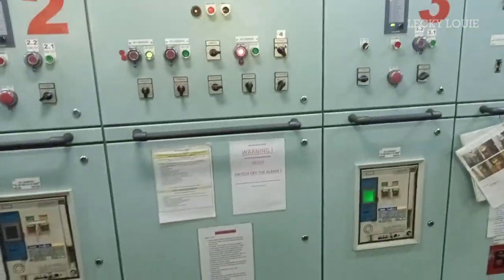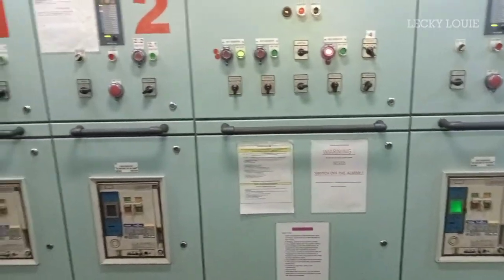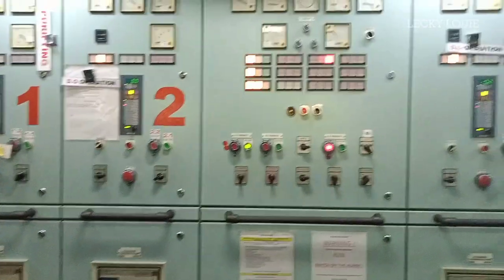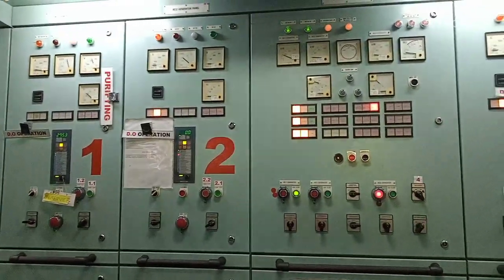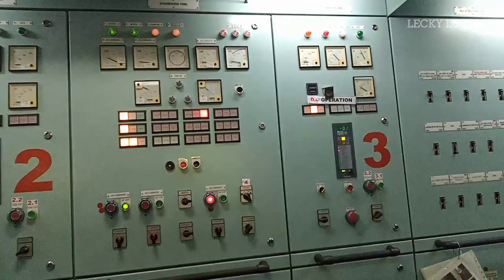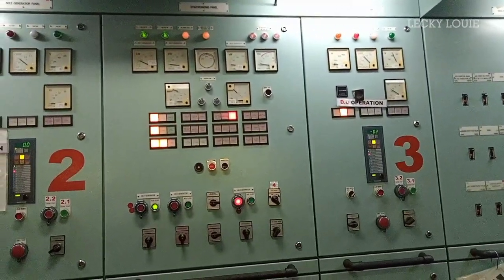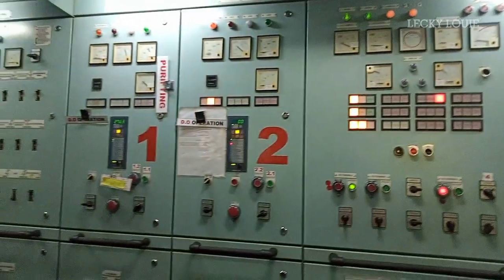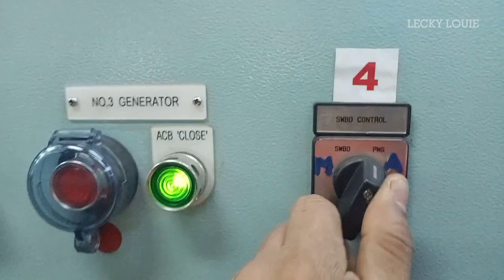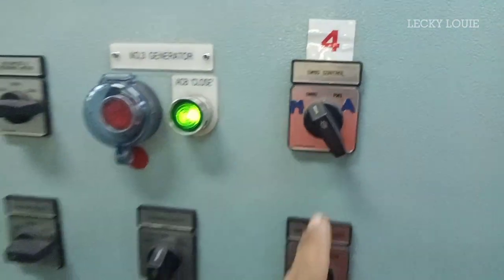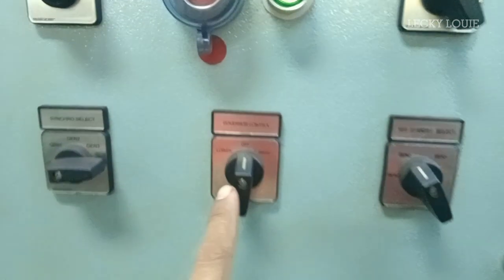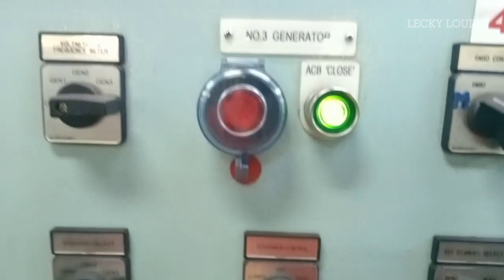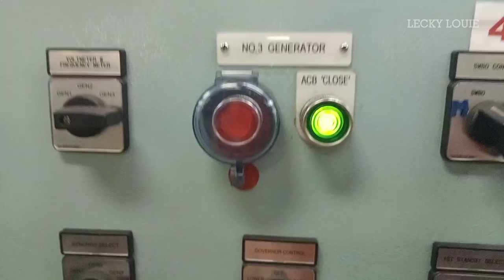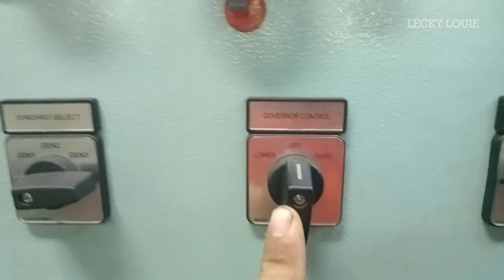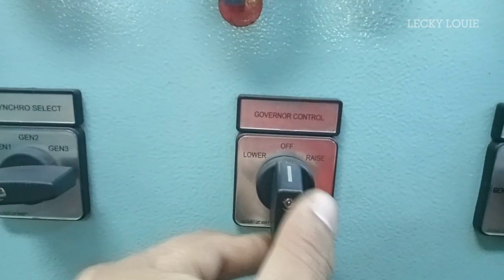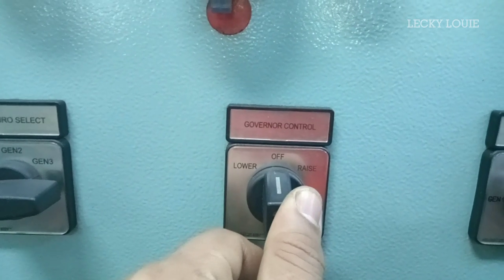Now, our generator number 1 and number 3 are running in parallel. We will test the reverse power alarm of generator number 3 and generator number 1 will remain in service to avoid system blackout. First, we need to set the main switchboard into manual mode load sharing. By means of the governor control knob, gradually decrease the kilowatt load of generator number 3 until it reaches about negative 75 kilowatts.